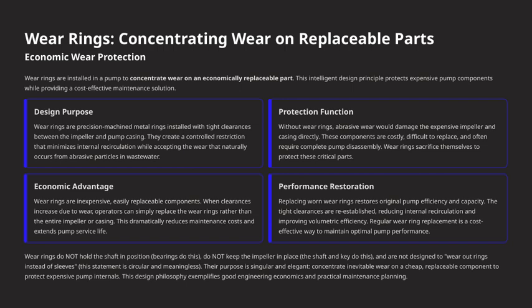It's important to understand what wear rings do and what they don't do. They do not hold the shaft in place. That's the job of bearings. They do not keep the impeller in position. That's the shaft and keys' role. And they are not designed to wear out rings instead of sleeves. That idea is circular and doesn't make sense. Their singular purpose is simply to concentrate wear on a cheap, replaceable part to protect the more expensive internals. This design philosophy exemplifies good engineering economics and practical maintenance planning, focusing on protecting critical parts while minimizing downtime and costs.